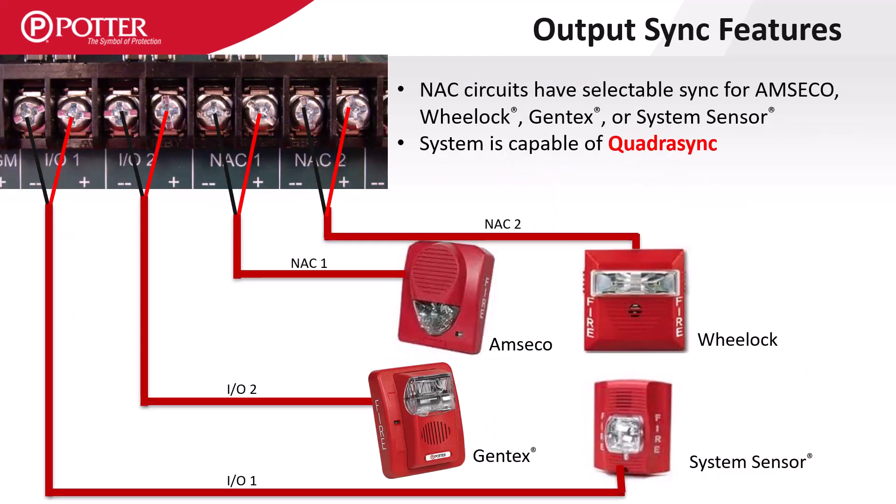Potter output circuits have the unique feature of QuadraSync, where there can be four different strobe sync protocols used on separate circuits, and all the visible appliances will synchronize. When using PSN1000 Intelligent Power Supplies, system-wide QuadraSync can be achieved.